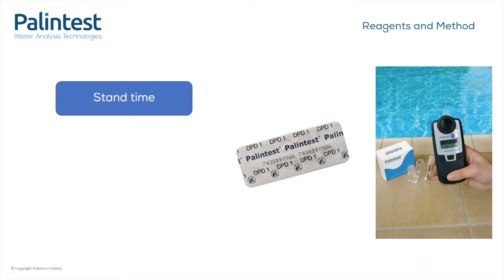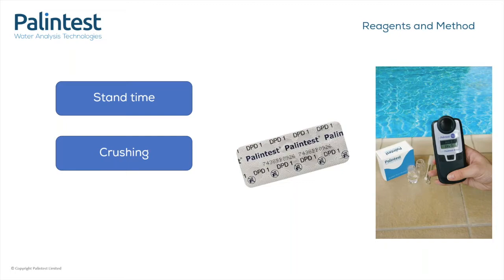On the larger photometers, there is a timer option you can use, although a stopwatch or phone app would work just as well. Another thing to consider is crushing. The crush rods have a teardrop shape to the end that can be used to break the tablet up initially without having to put too much pressure on the tube wall. For example, it's important to ensure that the tablet is fully crushed as this releases the chemicals from the tablet into the sample and allows the reaction to take place. Any uncrushed tablet will affect the reading, so it's important to both crush and mix effectively.